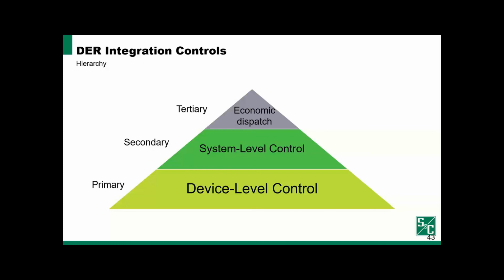Sitting above that, we have a system level control or secondary control. This typically operates on the scale of hundreds of milliseconds or seconds. The system level control typically will communicate with device level controls that are downstream of it and ensure it understands the status of all these device level controls, or the devices that are controlled at the primary level, as well as issuing commands to ensure that primary level devices are operating appropriately for the system needs at any given time.